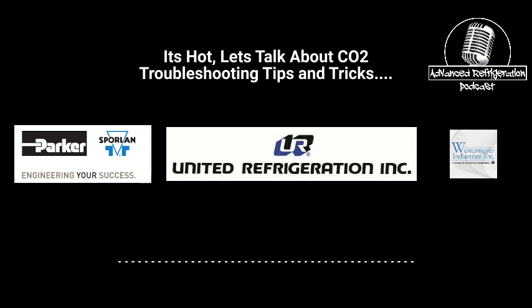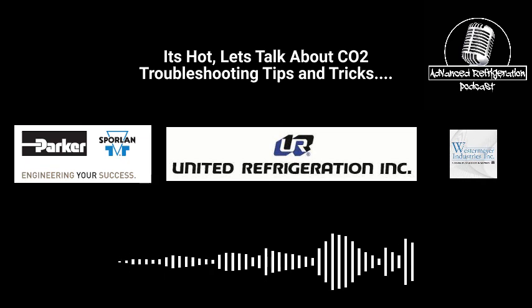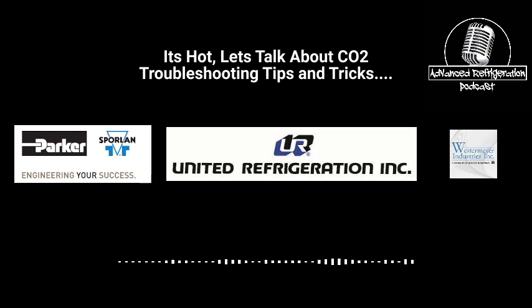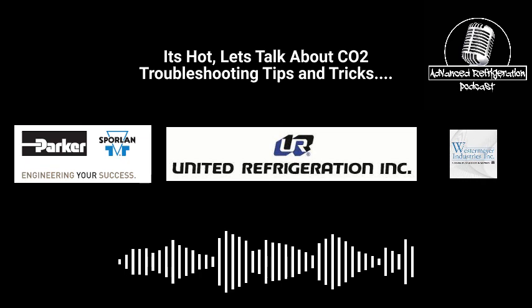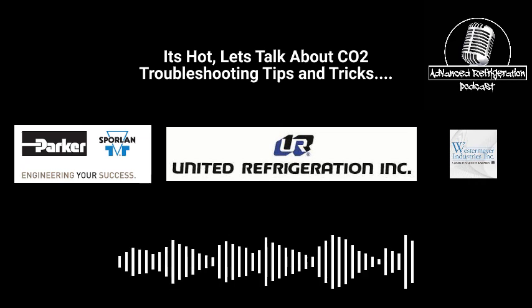Gotcha. I've seen more flash gas bypass valve failures than high pressure valves. I've never seen a high pressure valve fail. But they don't get driven like that. Generally on a well-tuned rack, the high pressure valve is fairly steady. It shouldn't be all over the place, as long as your drop leg or your drain leg or your gas cooler isn't all over the place, it should stay pretty steady.